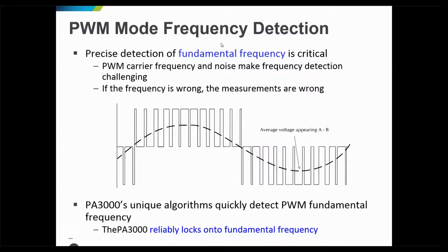This is very important, as the output of the PWM motor drive is a high frequency pulse width modulated voltage signal that has an underlying average sinusoidal wave at a frequency equivalent to load current. It's important to acquire the fundamental load frequency to accurately measure output power. The PWM mode uses a complex algorithm to digitally acquire the fundamental load frequency, which is different from your switching frequency, while preserving all the frequency components of a high frequency PWM signal. This is done for accurate RMS values.